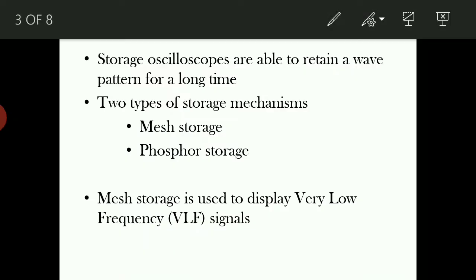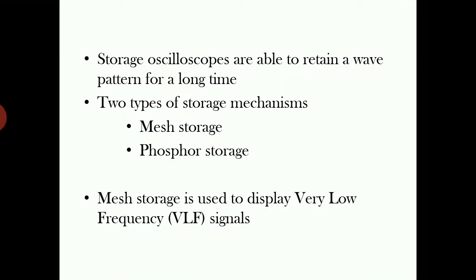Now, when we come to a storage oscilloscope, the main addition is that we have a storage mechanism. A storage oscilloscope is able to retain a waveform for a long time. In a CRO, we can have only instantaneous signals — once the signal is removed, no output will be displayed. But in the case of a storage oscilloscope, it can store that signal for a long time and display the same signal even after the signal is removed.